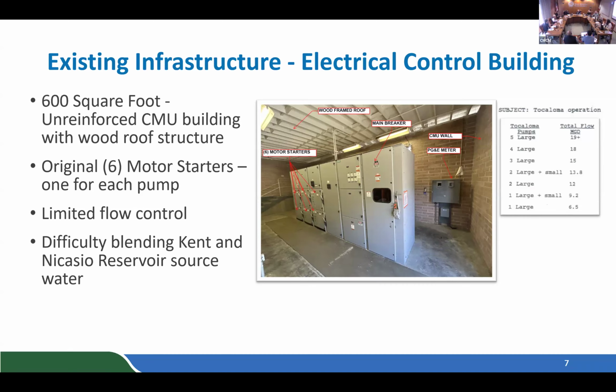I think you should also point out that what goes along with the PG&E bill is the demand charge. Correct. Which is substantial. Correct. And this is exactly what you're talking about, is reducing the demand charge. There's 2 measurements on electric meters for big power like this. One is the amount of kilowatts used. The second is how you use it. Correct. And they nail you for your highest demand for the month, whatever that number is. So when you flip that switch, you create a huge inrush of current. Correct. And a huge boost to the bill. Correct. Yeah, that's exactly right, Director. And the VFDs will allow us to slowly ramp up that motor, which reduces that inrush and those initial charges.